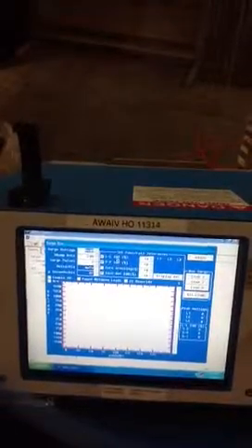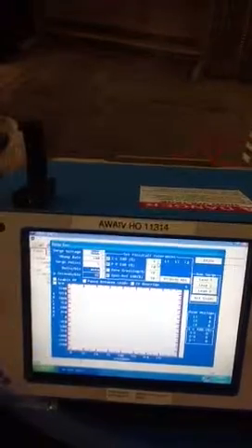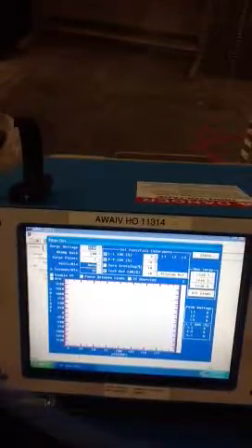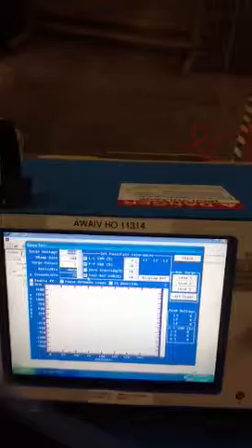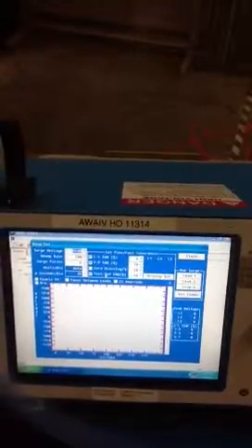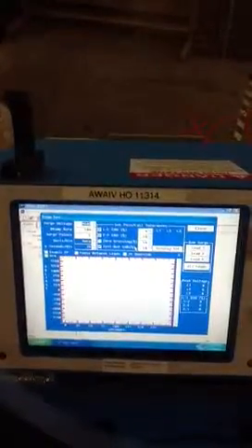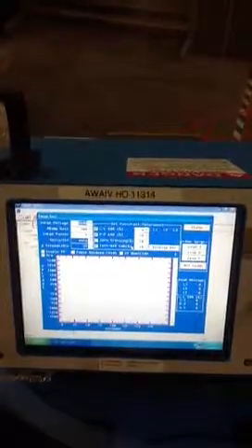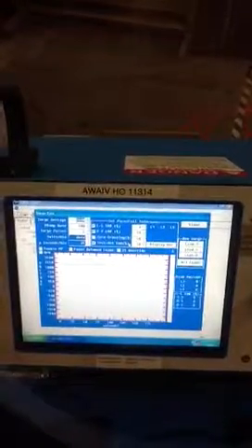Next thing we're going to do is set our line-to-line EAR values. I'm going to drop this down to about a 4% difference. Pulse-to-pulse is always set at 10. Zero crossing is always turned off, so don't check it. And then we're going to select the test reference.